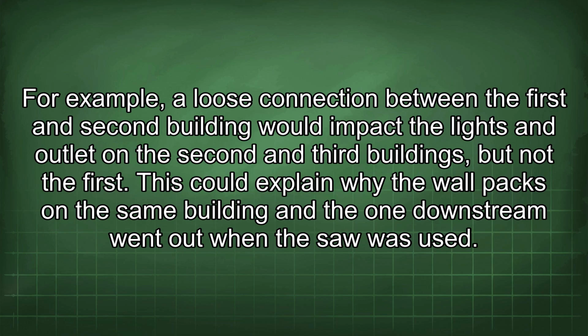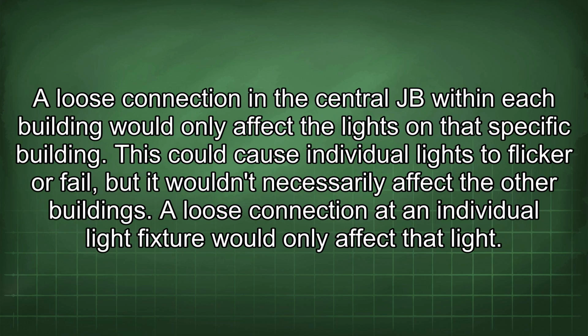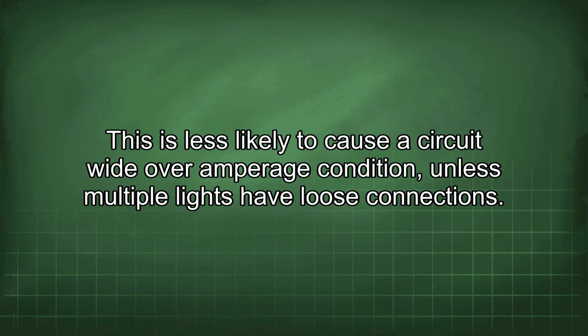This could explain why the wall packs on the same building and the one downstream went out when the saw was used. A loose connection in the central JB within each building would only affect the lights on that specific building. This could cause individual lights to flicker or fail, but it wouldn't necessarily affect the other buildings. A loose connection at an individual light fixture would only affect that light. This is less likely to cause a circuit-wide overamperage condition unless multiple lights have loose connections.